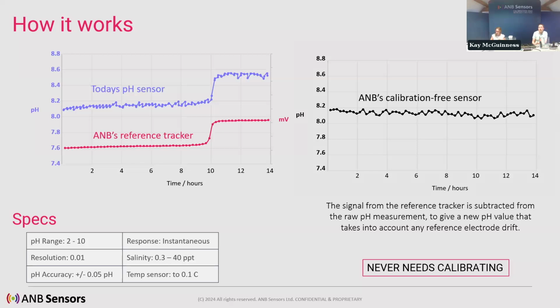Brilliant, thank you. Maybe if I put up the tools, you can talk about how it's different from the glass electrode. Yes, exactly. So why are we different? Well, obviously we are calibration-free. We're all solid state, so this is one of the sensors here. Completely solid state, no glass involved at all. Therefore, it's robust and stable. You can drop it, it doesn't smash. Also, it doesn't need to be stored wet. It can be stored wet or dry, just leave it on the shelf. No difficulty there. When you deploy it, just turn it on and throw it in the water, and it's good to go.